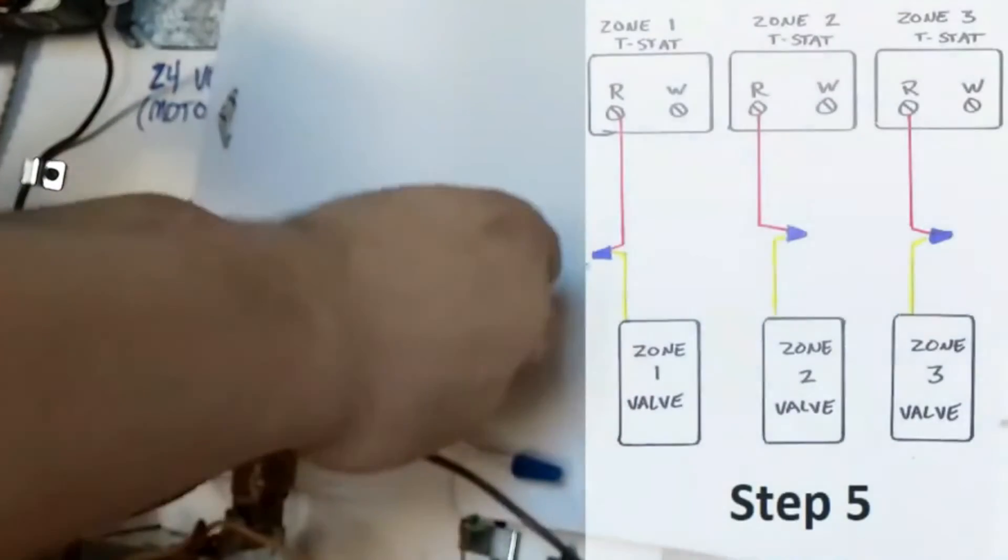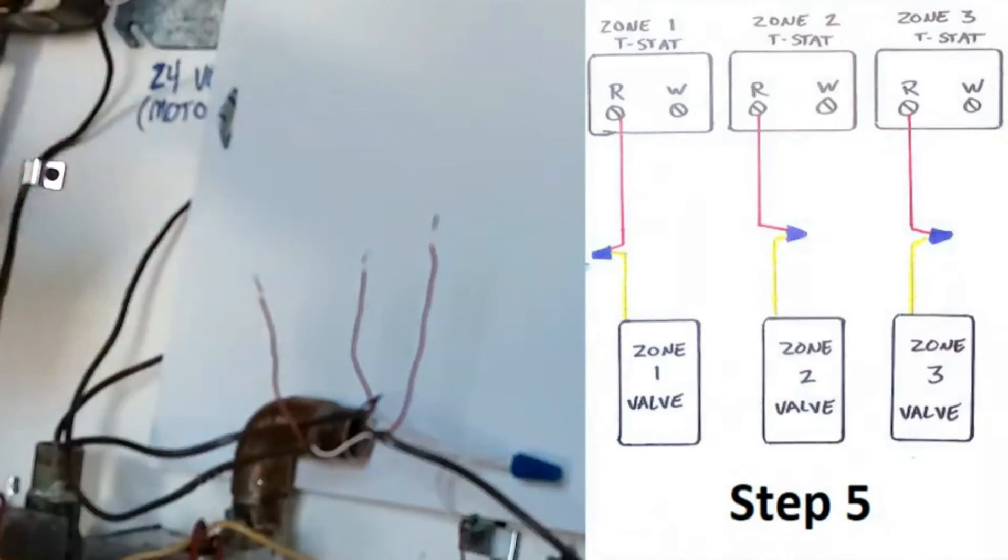So now what we have left for step five is one red wire from each thermostat and these are the wires that go to your R terminals and we're going to hook those up to each one of the yellow wires left on our zone valve.